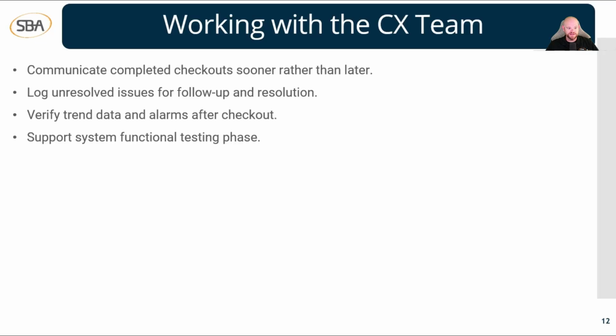The next is to verify trend data and alarms after the checkout. So make sure that your trend data has proper trending in there. Also, make sure that your alarms are triggered when they're supposed to be. Go back and verify all those.